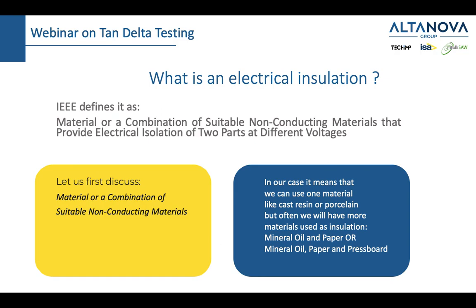Obviously, we can have only one material as an insulator. For example, it can be just cast resin in a dry-type transformer, or porcelain in a bushing. But very often, in a power transformer, we will have a mix: mineral oil and paper, or mineral oil, paper and pressboard. This is important because later we will refer to this definition and see why tan delta is so good, and I'll give you a hint. It's good because it doesn't measure the insulating properties of only one material in this set of materials. It gives us an idea about the whole insulating system which we have installed.